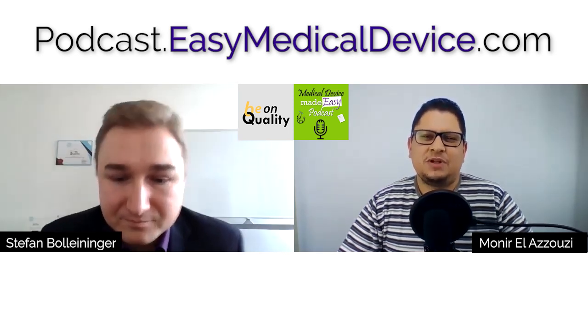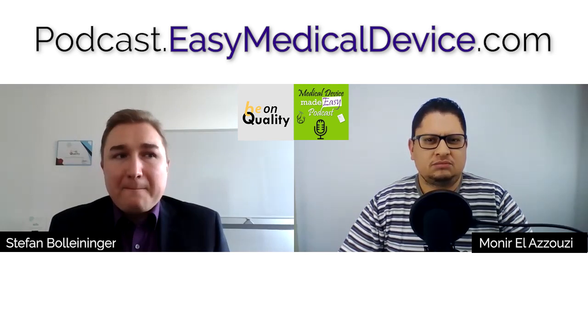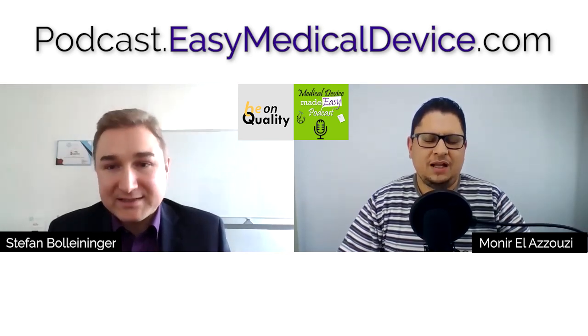So mainly, when we say we need the quality management system, you already mentioned that we have the ISO 13485, which is a quality management system for medical devices. So this is mainly what is recommended by the MDR. The MDR does not tell us which one we shall use, but there is always a but in that sentence: one day we will have the harmonized standards, and it is nearly safe that we will need to comply with ISO 13485 as a harmonized standard.